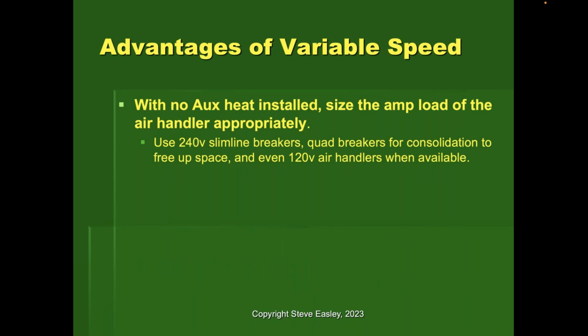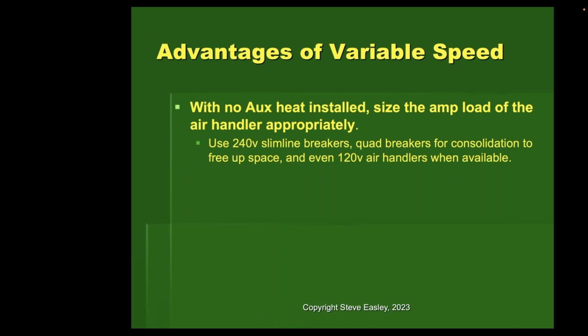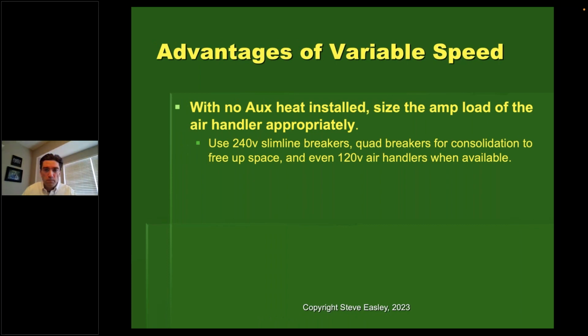So bottom line is, with no auxiliary heat installed, we size the amp load and air handler appropriately. Use 240-volt breakers, obviously, for that. And you can use these slim lines that allow you to free up some space. So those of you that have existing homes, what I'm trying to say here is that oftentimes when you have existing homes and minimal panel sizes and you're trying to electrify, it becomes a little bit challenging, because how do you get enough breakers in the box and still meet all the electrical codes for fire and safety, right? And so I'll give you an example.